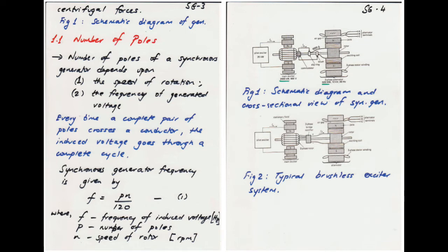So the system is, you have a pilot exciter, right, which produces the field on your main exciter, and the conductors mounted on the exciter look like a DC machine, right? It's connected to the commutator and slip ring, right? And from there, you're getting your DC current that's being fed to the rotor field circuit, right? As you can see, the rating of your main exciter is around 2,400 kilowatt, right? And that's producing a field current of 6,000 amps that you require on your rotor side. This is for a large machine which is rated at 500 megawatt.